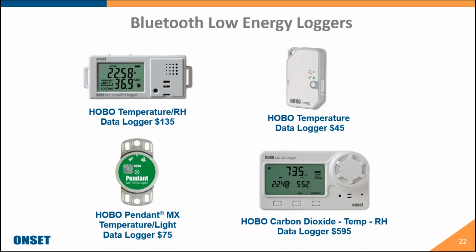And then this is one of our more unique loggers for the fact that while it is Bluetooth, there is actually a USB port on it, which would allow you to connect to a computer through that USB cable running our HoboWare software to do your configuration and data offload. And we also do sell a power supply for it that you could connect in for long-term deployment, so you wouldn't have to necessarily be reliant on the batteries. One nice feature with that is it can run off of that AC power, and if for some reason your facility was to lose power, the data logger will still continue to record using that battery backup.